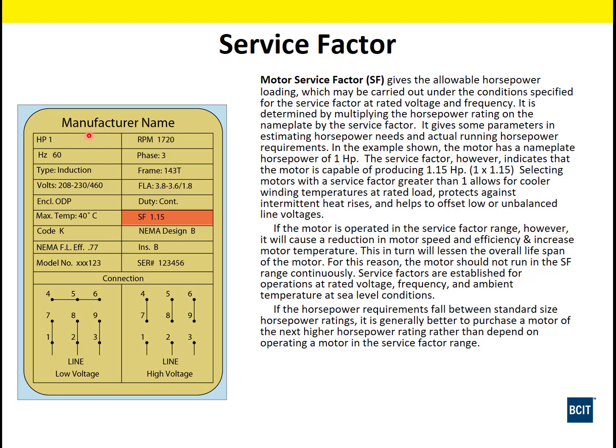Because we technically can run this motor at, let's say we've connected it up to 460 volts, we should be able to run this motor continuously at 1.8 amps forever. It should function fully and perfectly at that amount. If we had no service factor and everything was sized for that maximum current, we eventually could be heating up the windings. The load is going to fluctuate. The current is actually, remember, RMS current also. So the peak current is going to be a little higher. That could over time heat up the windings and prematurely cause failure.